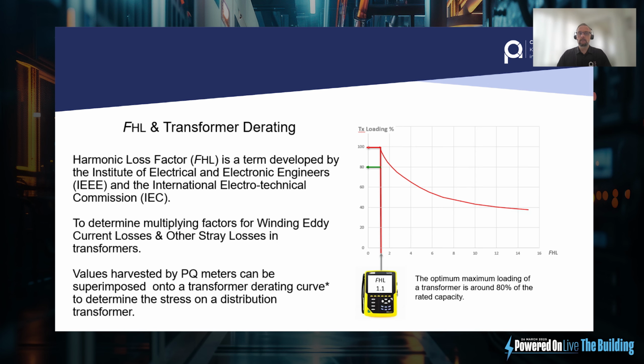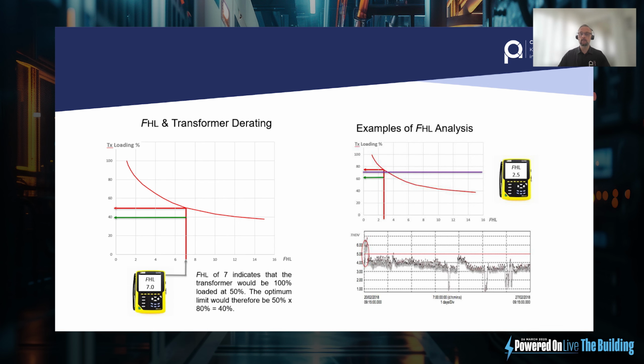And another thing that's not really mentioned much is something called harmonic loss factor. So these harmonics feed back to the transformer and summate there. And in FHL, if we breach that curve, what we can see is that the voltage distortion from the transformer increases and the ability for the transformer to provide you enough power for your loads gets reduced. So an example here is if we had an FHL of 7, you can see on the left-hand side, the transformer would be derated to around 50% of its capability.